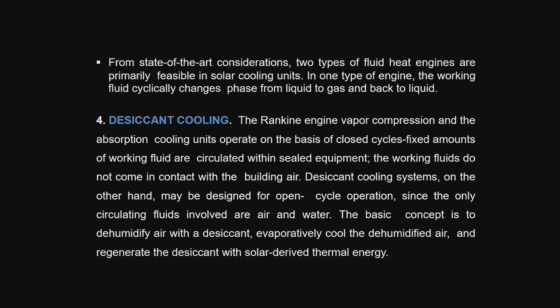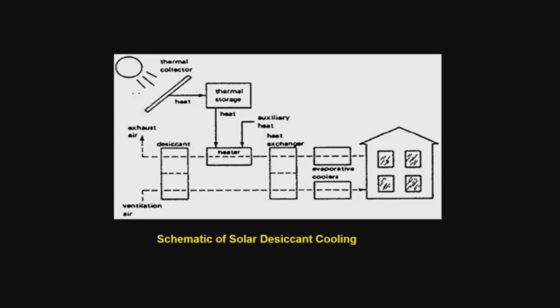Desiccant cooling systems, on the other hand, may be designed for open cycle operation, since the only circulating fluids involved are air and water. The basic concept is to dehumidify air, then evaporatively cool the dehumidified air, and regenerate the desiccant with solar derived thermal energy. In the schematic diagram of a solar desiccant cooling system, we see the thermal collector, heater and auxiliary heat exchanger. This shows the desiccant cooling of a solar cooling system.